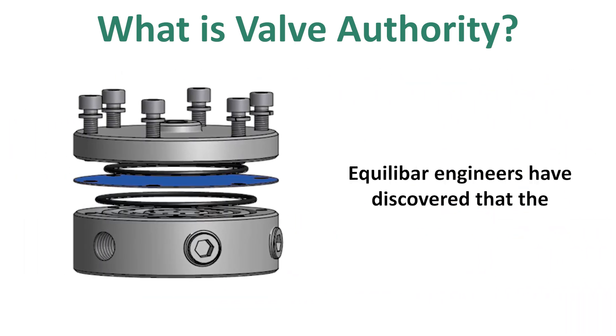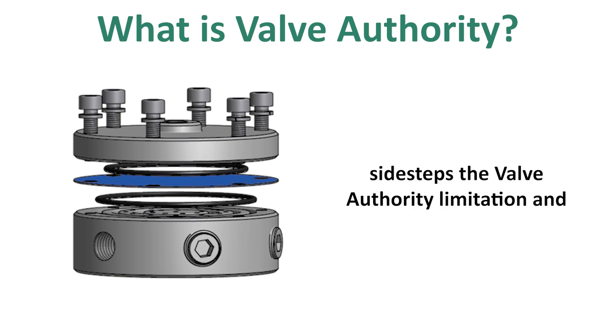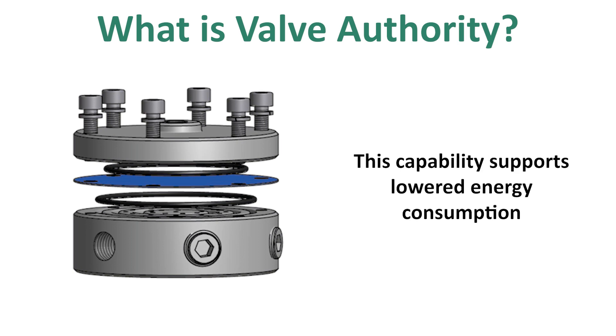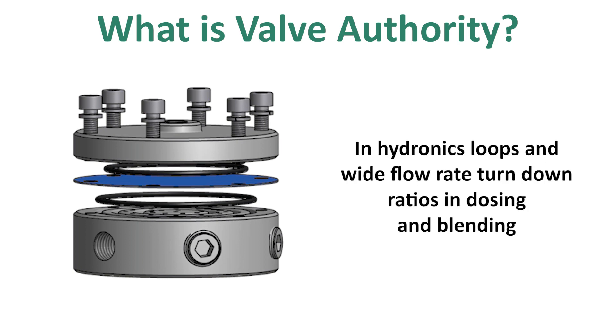Equilibar engineers have discovered that the 1000 to 1 turndown of their novel control valve sidesteps the valve authority limitation and provides stable control of ratios down to 1 or 2 percent. This capability supports lowered energy consumption in hydronics loops and wide flow rate turndown ratios in dosing and blending, up to the limitation of the flow meter.